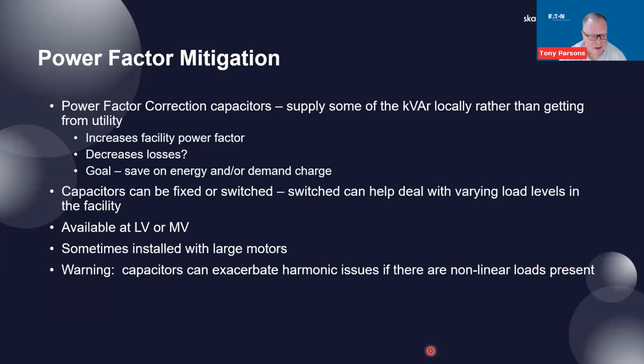But as we just saw, and we saw the aftermath on the last slide, the big warning: capacitors can exacerbate harmonic issues if there are nonlinear loads present. So application of power factor correction capacitors is not just as simple as looking at your bill, figuring out how much kVAR you're using, and then selecting something out of the catalog, right? We really need a little bit further analysis to make sure that you're applying the right type of equipment in your system.